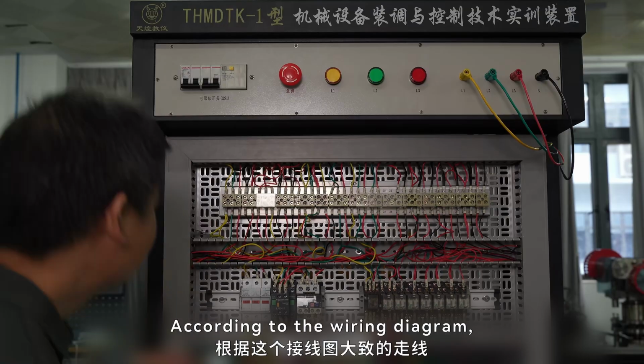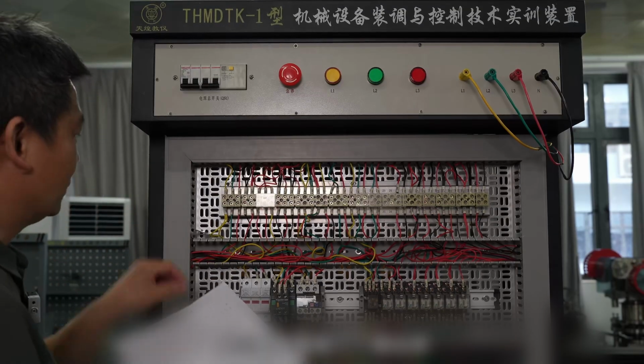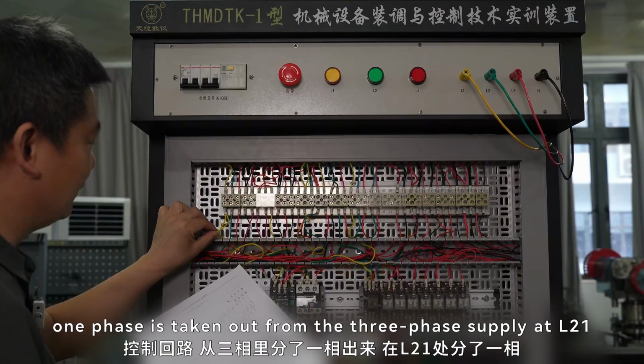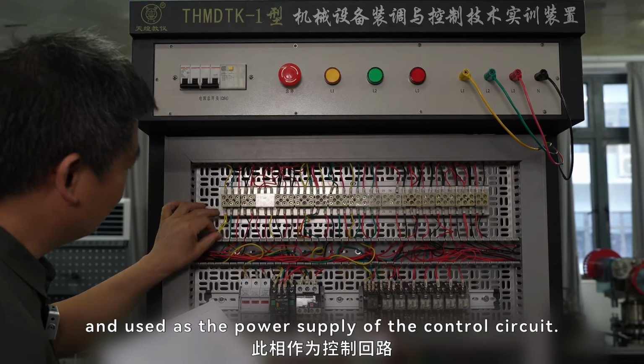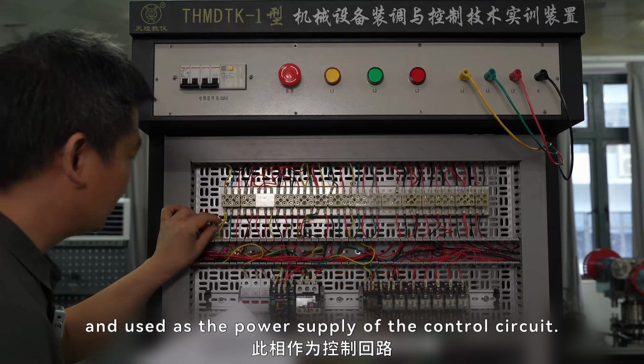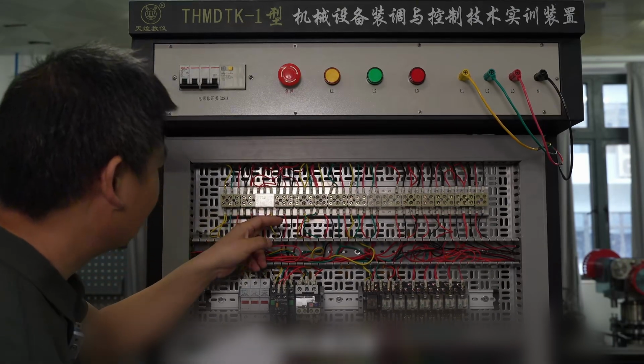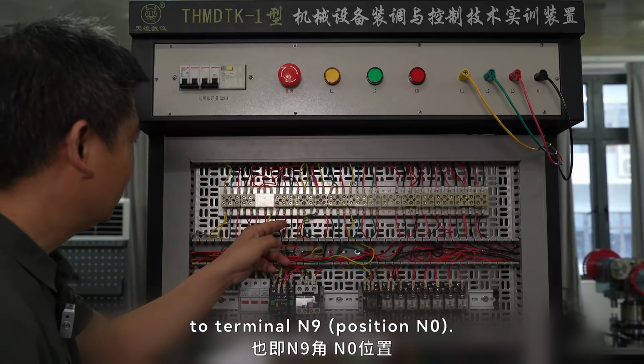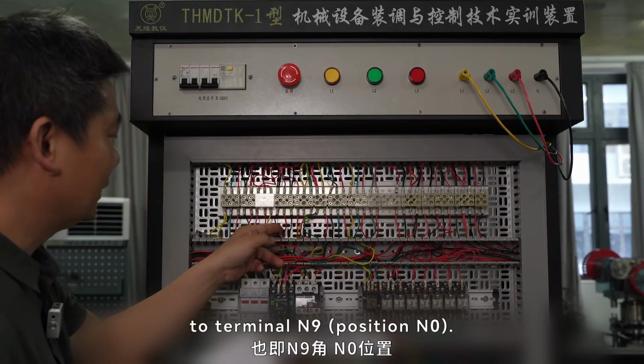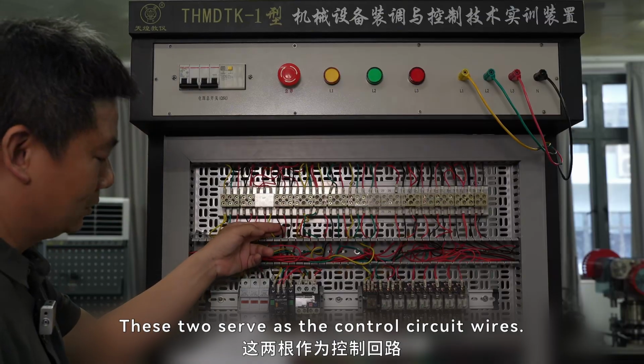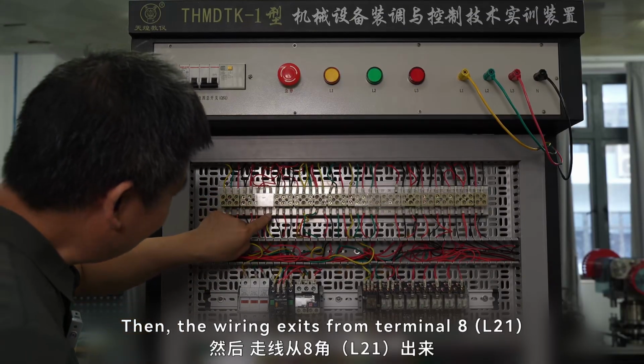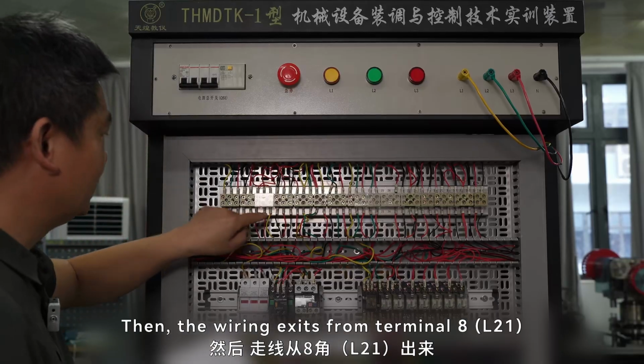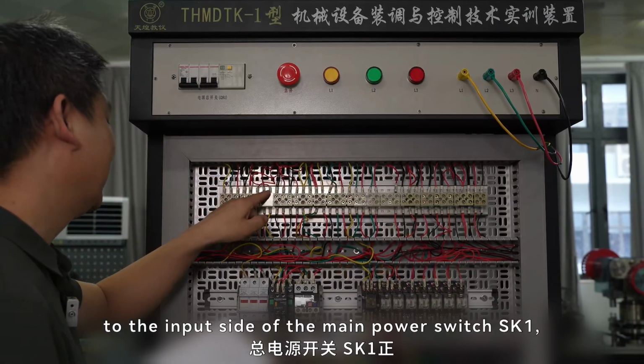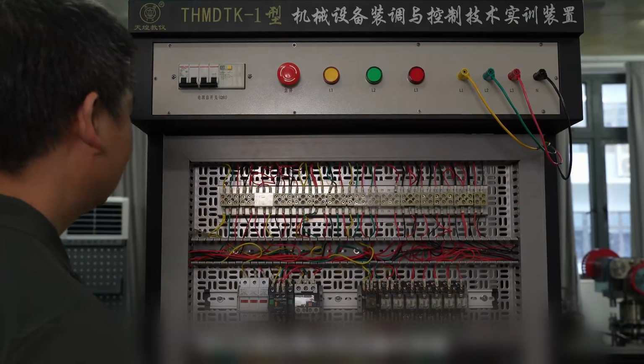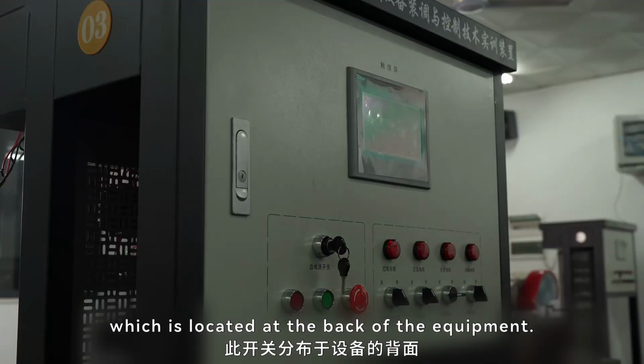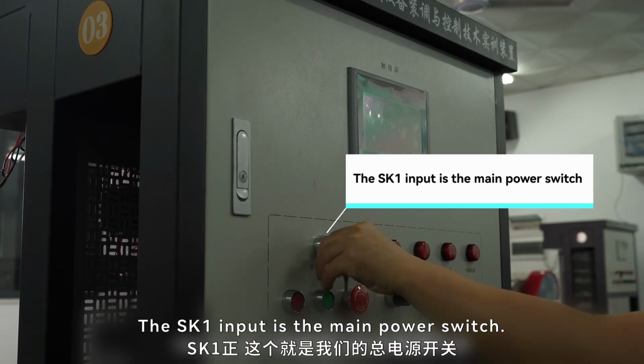According to the wiring diagram, the general wiring goes like this. First, one phase is taken out from the 3-phase supply at L21 and used as the power supply of the control circuit. It is connected to terminal 8, and the ground wire is also connected to terminal N9, position N0. These two serve as the control circuit wires. Then, the wiring exits from terminal 8, L21, and connects to the input side of the main power switch SK1, which is located at the back of the equipment. The SK1 input is the main power switch.